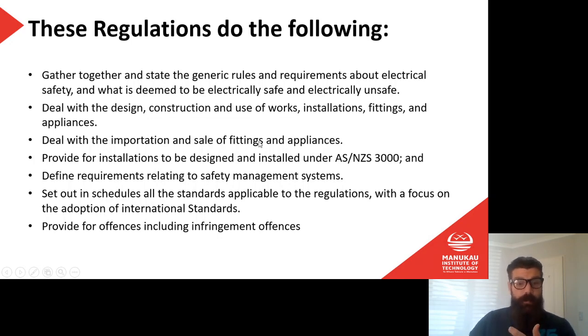They deal with the importation and sale of fittings and appliances. Remembering that when we import stuff from overseas, there must be some method of ensuring that those are safe and approved for use in New Zealand. They provide for installations to be designed and installed under AS/NZS 3000. So the regulations reference the standard, and that gives us the authority to use that standard as a means of complying with the regulations. The regulations will tell us that everything needs to be safe, but it's general. It doesn't tell us how to do that. So it says go and have a look in AS/NZS 3000. That's where you get that specific information. So the regs refer to that standard.